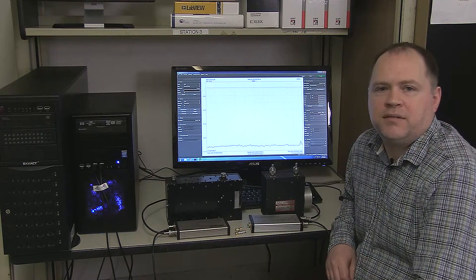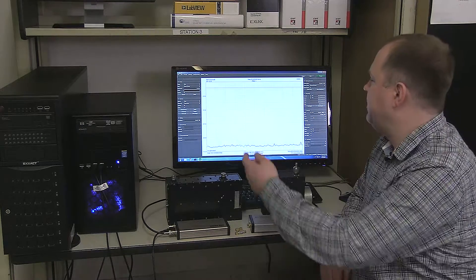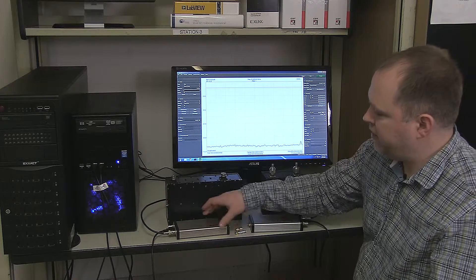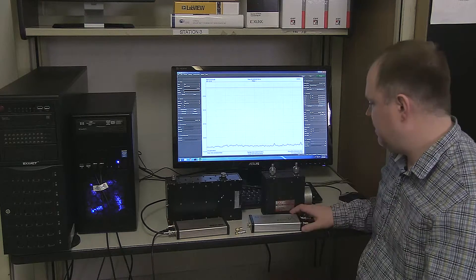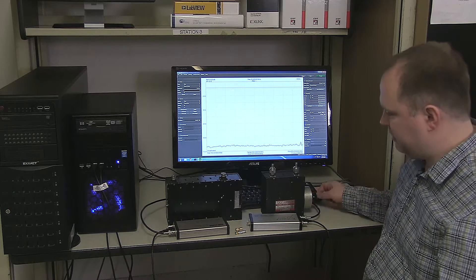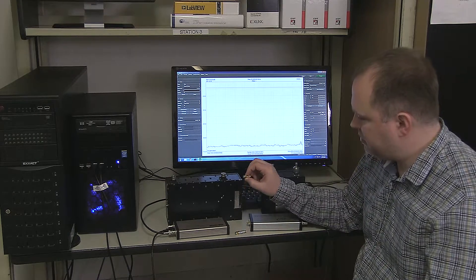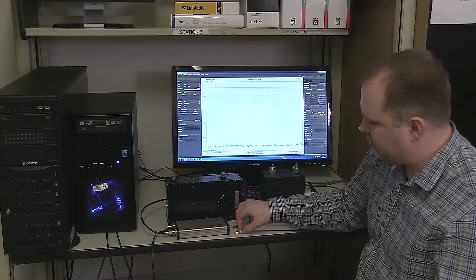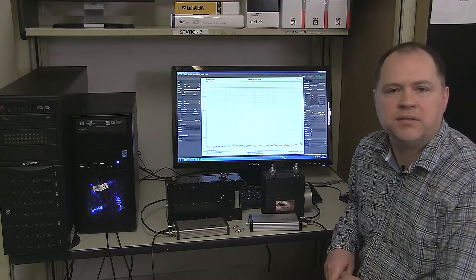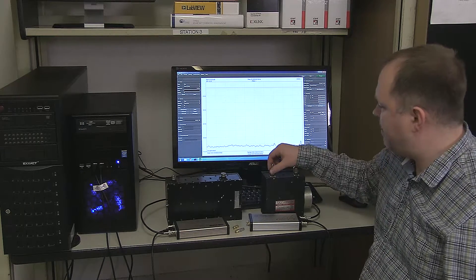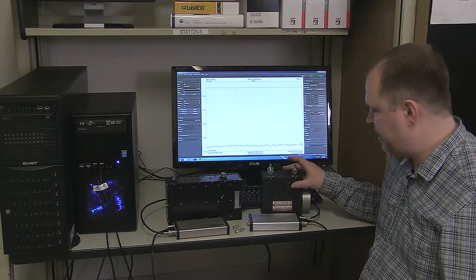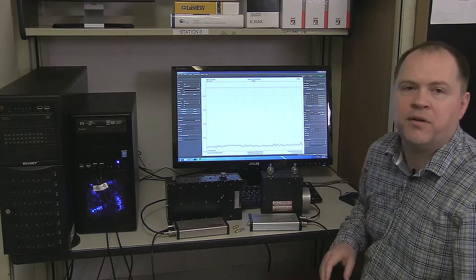To measure insertion loss, you will need a PC or laptop with the Spike software installed, a USB SA44B with a USB cable, a USB TG44A with USB cable and BNC cable, a 0 dB insertion loss through, and a 20 dB pad to calibrate the gain difference between the high and low gain ranges. And finally, you'll need whatever adapters are required to connect your device under test to your SA44B and TG44A.